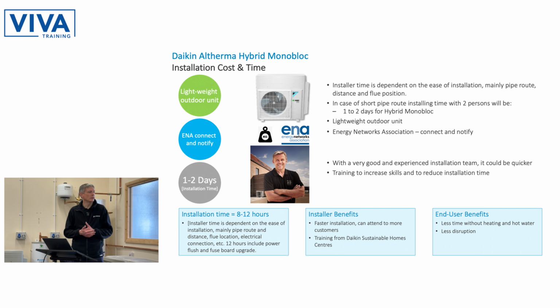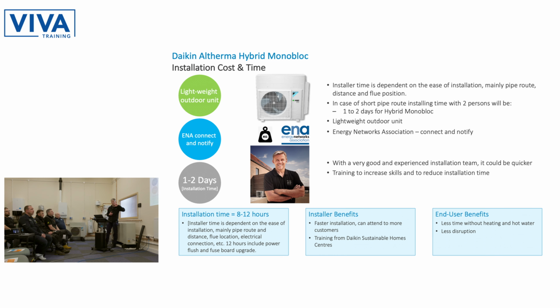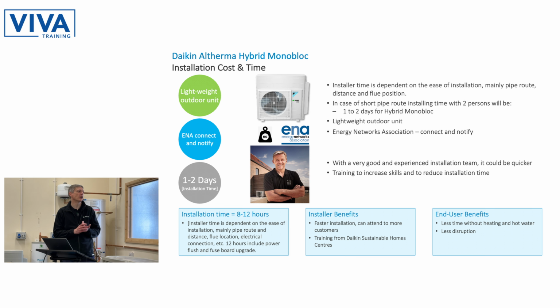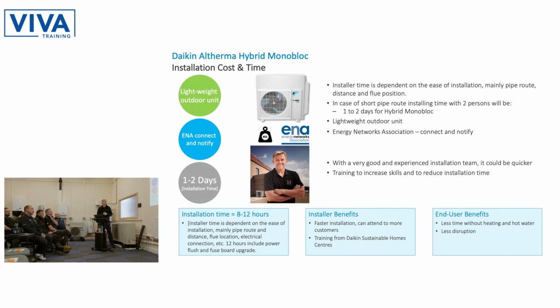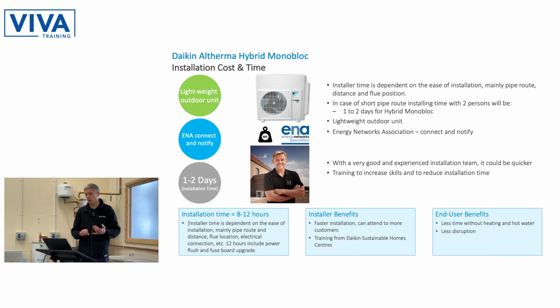We looked at 8 to 12 hours being typical, where you've got the heat pump on the other side of the wall from the boiler, so a relatively short pipe run. If it's further, that might increase your installation time a little bit. That 12 hours also included flushing and upgrading the fuse board. Familiarity would get those times down, but 2 days should cover it for most installations. That means more jobs, more heat pump installations, and the training to benefit from that is available from us, and from sustainable home centres such as Viva Training. So it's less disruption, and less time without heating and hot water for the homeowner.